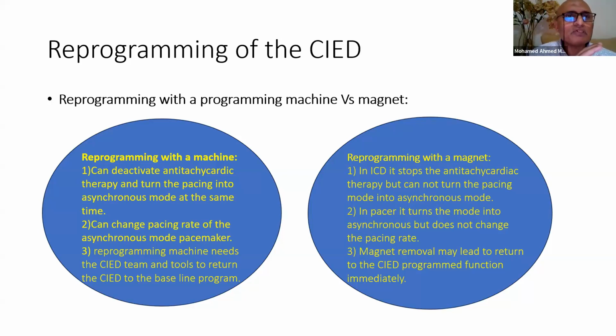The reprogramming machine can convert the pacing from synchronous mode to asynchronous mode. We need the pacemaker to work asynchronously during the operation, so this can be done using the reprogramming machine. While if we reprogram with a magnet, when it is applied on an ICD, it will stop only the defibrillation function. But the magnet has no effect on the pacemaker of the ICD. It cannot turn the pacemaker of the ICD from synchronous to asynchronous. It cannot increase the pacing rate of asynchronous mode of the pacemaker of the ICD. So if we have an ICD, the magnet has a limited effect only on the defibrillation function of the ICD, but it does nothing with the pacemaker of the ICD.